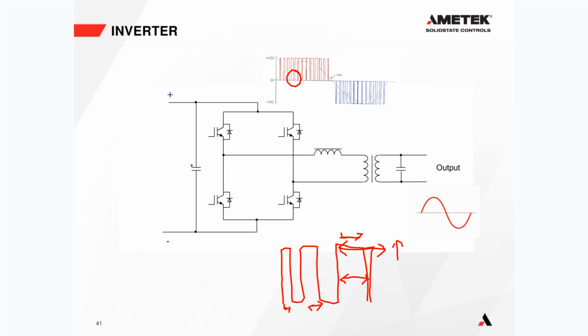So we are constantly monitoring the DC going into our inverter bridge and the requirements of our load circuits using a feedback mechanism. We're looking at the output and at the DC input, constantly adjusting every single pulse to make sure we get 120 volts on the output. For example, if the battery voltage goes down, the height of this pulse goes down, so the area under the curve goes down. So we make this pulse a little bit wider now, so the area under the curve goes back up to regulate.